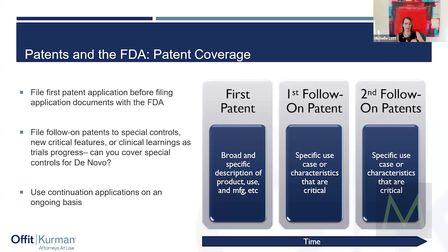To your second point there about the special controls for a de novo, I think companies also underestimate the power of being able to set the standard for subsequent 510(k)s by defining the special controls. You can tell when the FDA issues a new regulation out of a de novo who understood it and who didn't, because I've seen some regulations that were 2 sentences, and I've seen some that were almost 2 pages worth of specifications that the product had to meet. The special controls are a barrier to entry, and a useful one. And I think smart use of that, as you described, is really important.